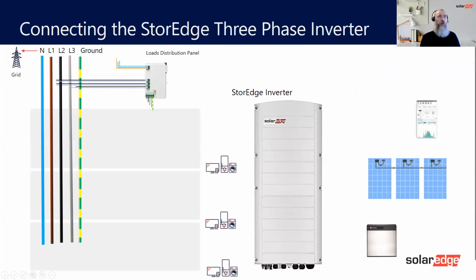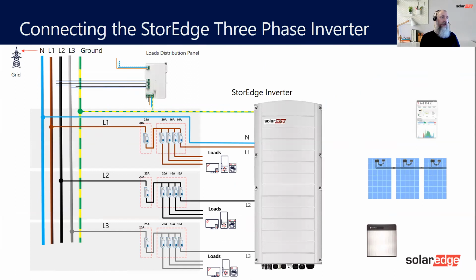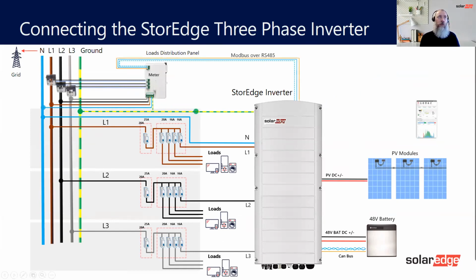Okay, let's have a quick look at what happens now. You can connect 3 different loads to it because obviously it's a 3-phase storage system. The meter itself will connect, and the battery will connect, and the PV connects to it. There's the meter connecting with the 3 CTs, 1 per phase. And please also note that L1 is connected to L1 CT, and also L1 is shown on here as L1. So please make sure the phases correspond. And then last of all, you've got your internet connection, which could be wireless, could use direct to the modem, or could be GSM. And you can see this on your monitoring platform as well.